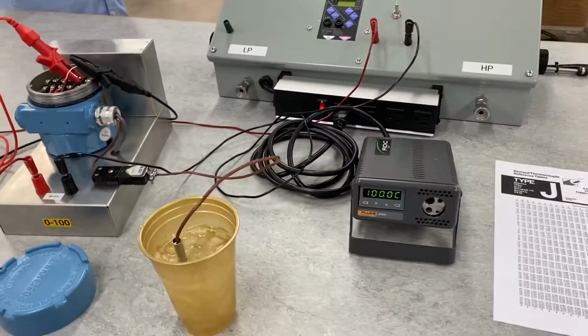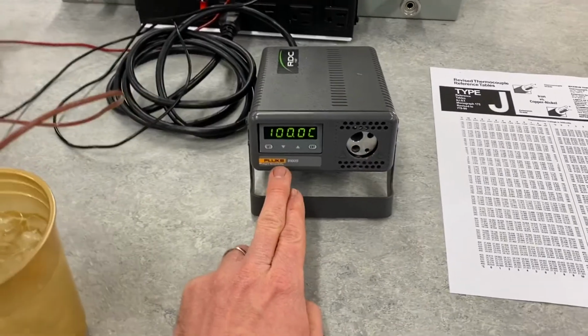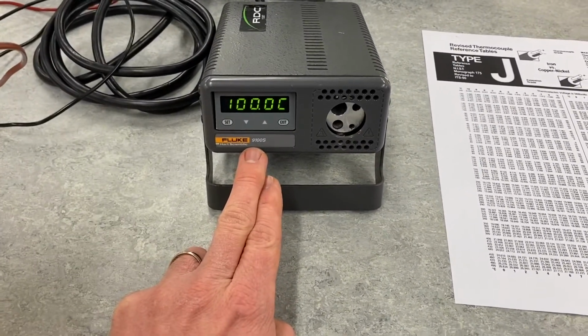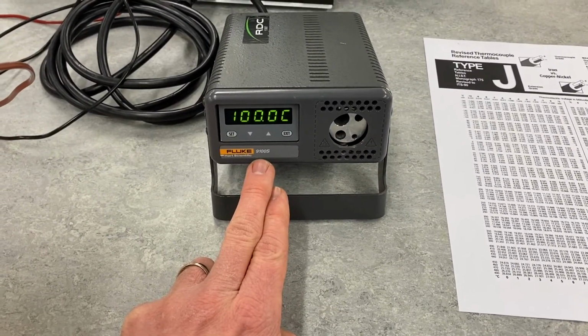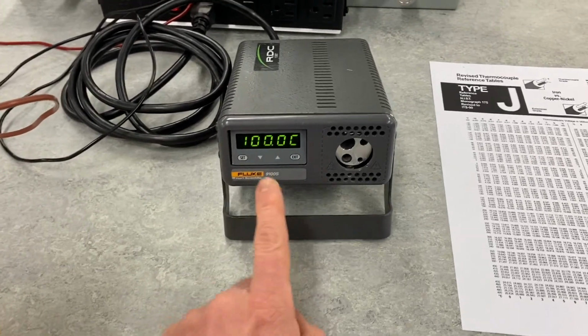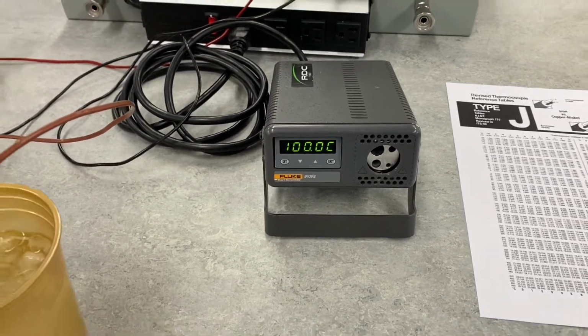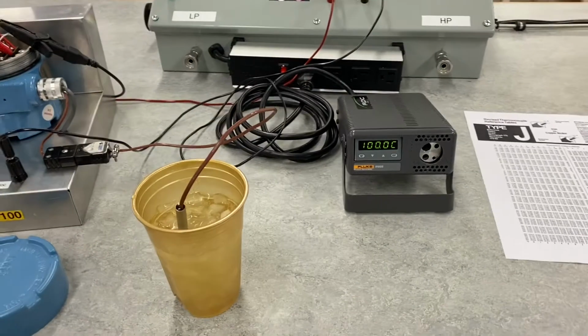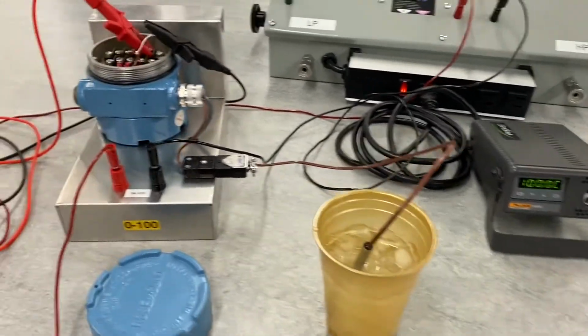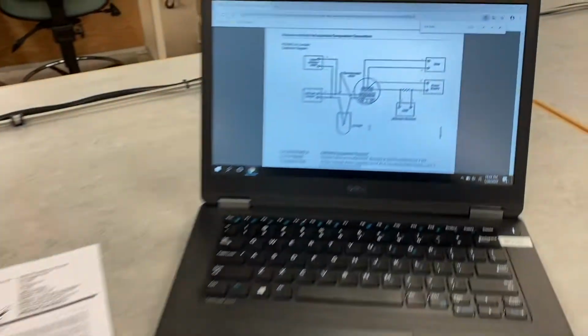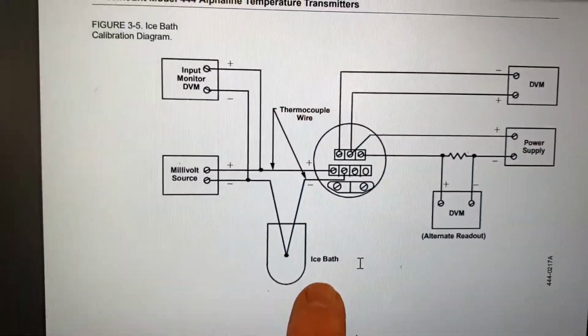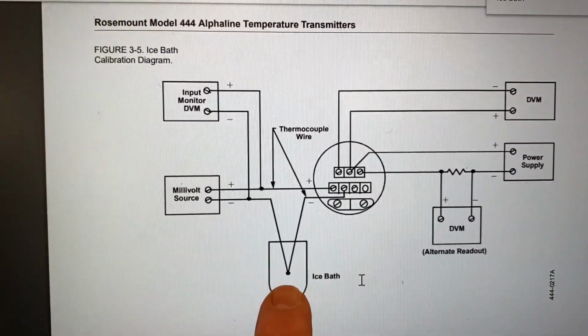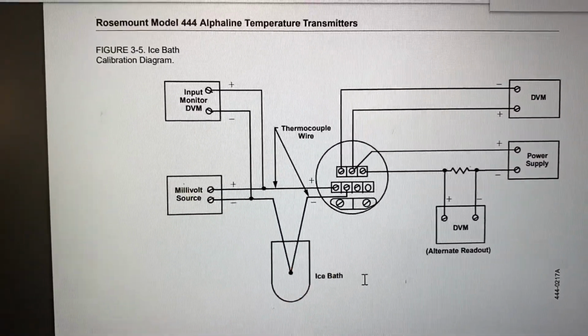So the first step here, we're eventually going to need our Fluke 9100S dry block calibrator. We want to turn it on and set it for 100 degrees C, so it's good and warmed up before we need it. The type of calibration we're going to be doing here is called the ice bath method, where we put the thermocouple in an ice bath here and wire it up as shown here.